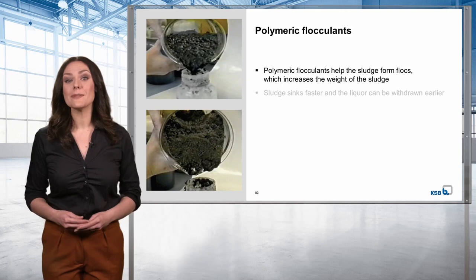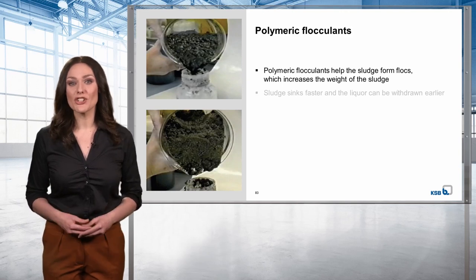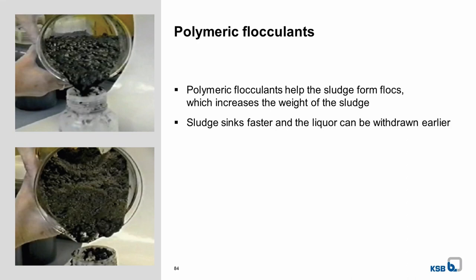In total, the thickening process takes quite a long time. This can be problematic because the larger the wastewater treatment plant, the larger the sludge volume. Secondary sludge in particular occurs very quickly in large volumes. To accelerate the thickening process, larger wastewater treatment plants add polymeric flocculants. They help the sludge form flocs, which increases the weight of the sludge. Consequently, the sludge sinks faster and the liquor can be withdrawn earlier.